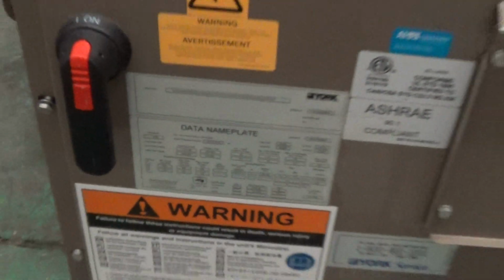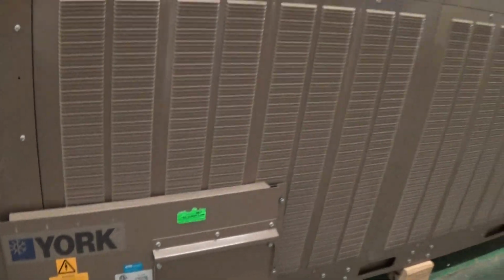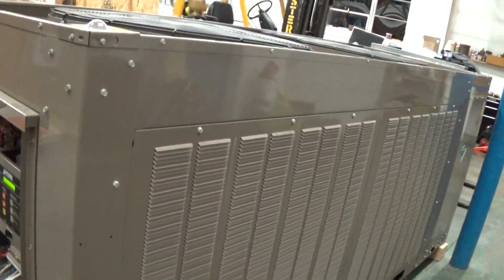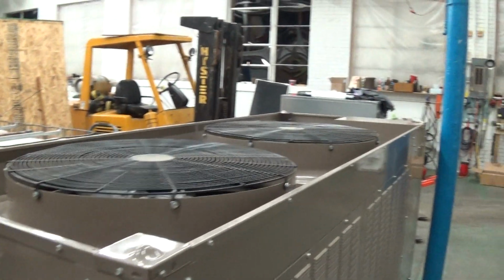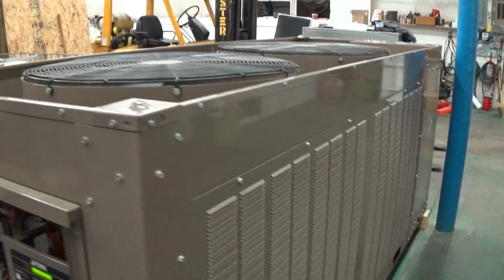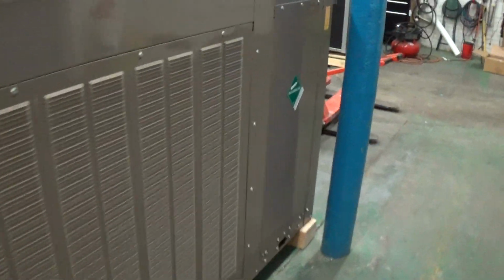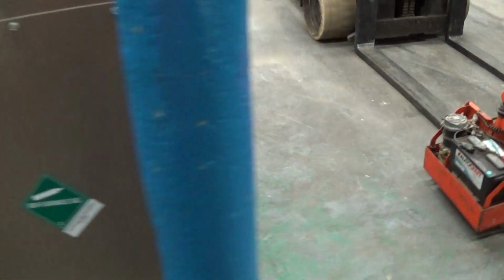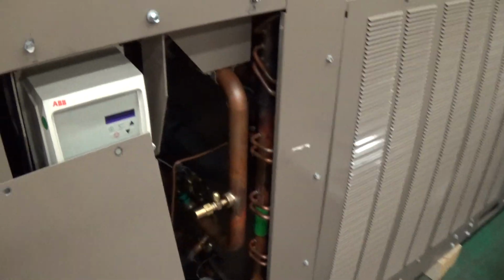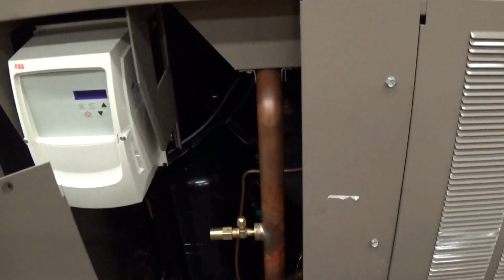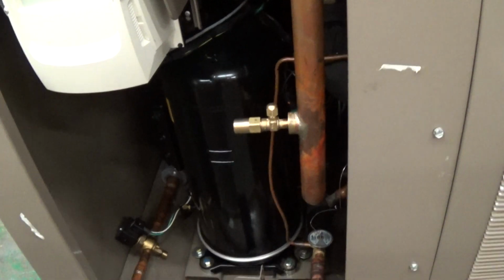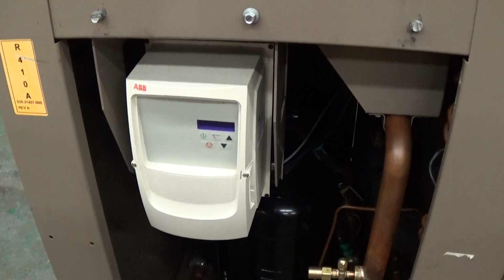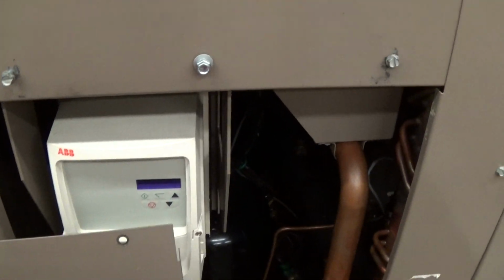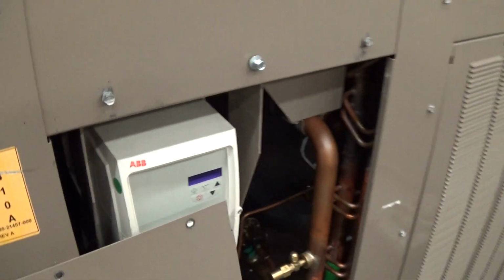The units that we stock all have common options, low and high ambient. So this unit has two fans here. One of them is controlled off of a VFD to achieve that low ambient. It's a single circuit chiller as far as refrigerant circuit goes, but it has two compressors. You can just barely see the second one back there. This is the VFD for the low ambient on the second fan.